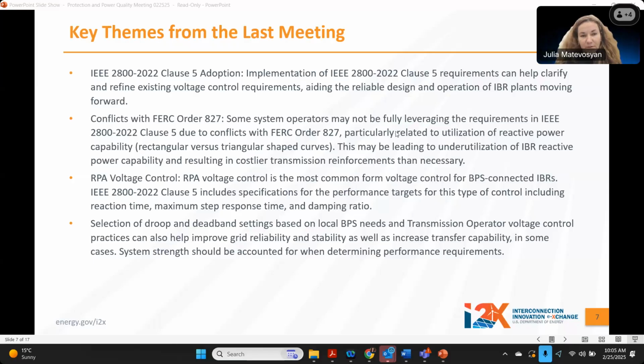We also talked about the reference point of applicability for voltage control. This is the most common place where the voltage is controlled. So if it's chosen to be a POI, then this is where the voltage control is applied for BPS connected inverter-based resources. And clause 5 of IEEE 2800 includes specifications for performance targets for this type of control, including reaction time, maximum step response time, and damping ratio. And then we also talked about selection of droop and deadband settings, that sometimes it makes sense to base it on local bulk power supply system needs and transmission operator voltage control practices. Choosing it in this customized manner can help to improve grid reliability and stability.